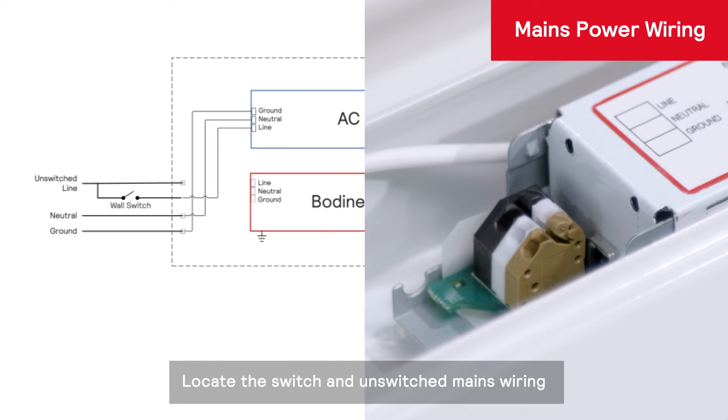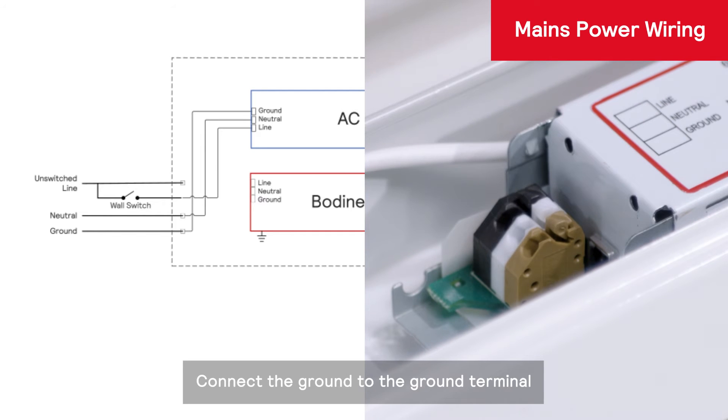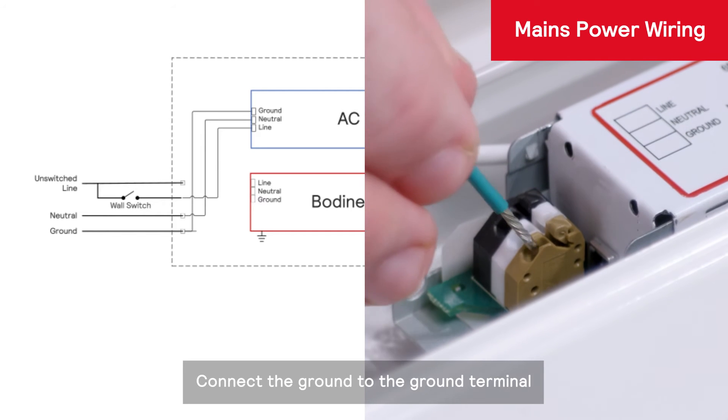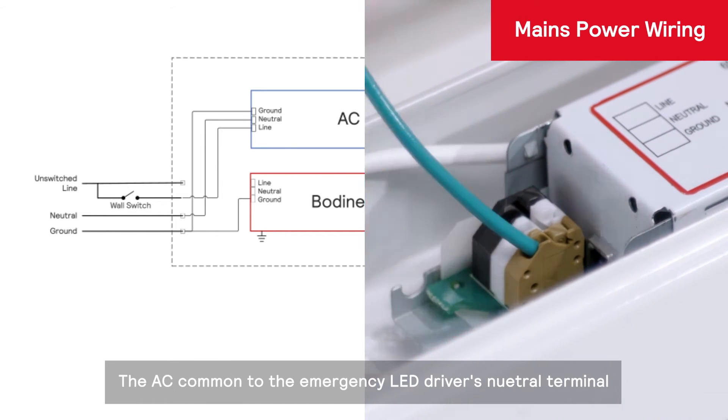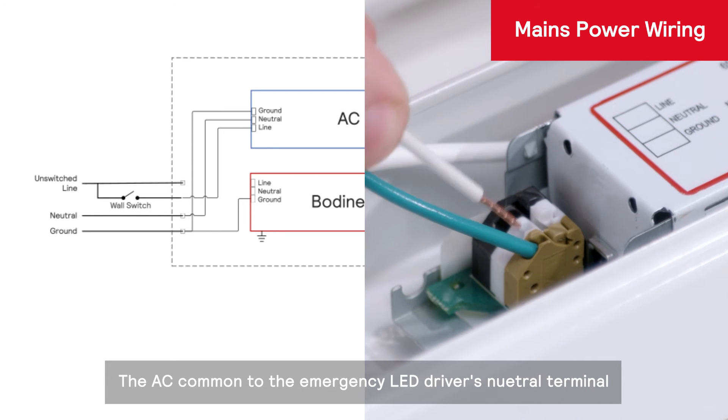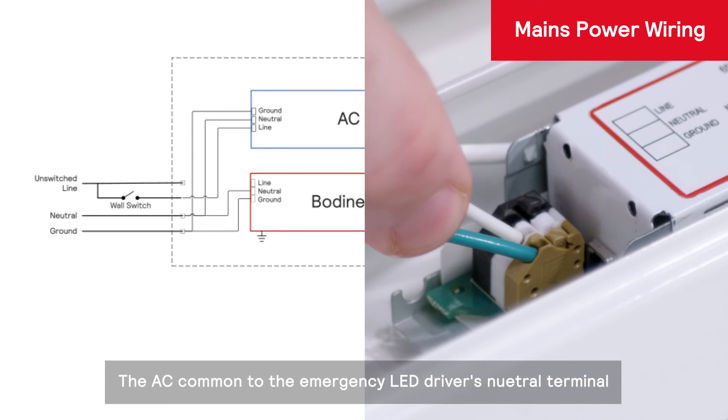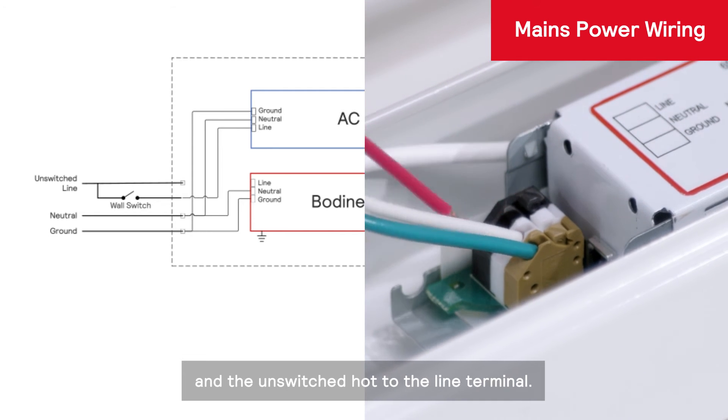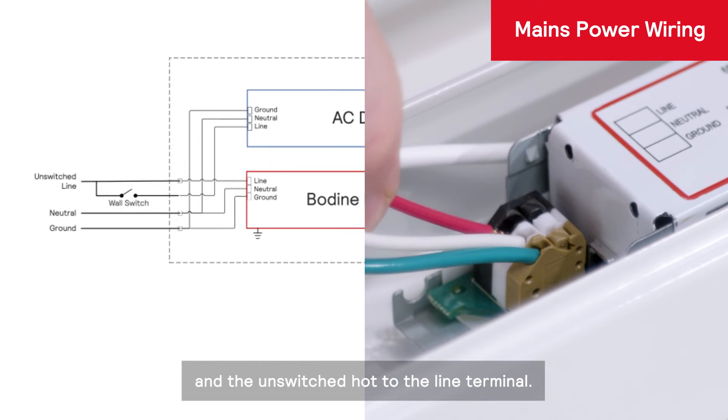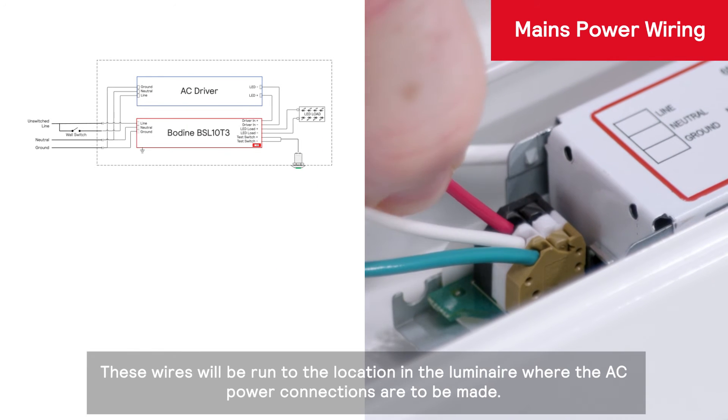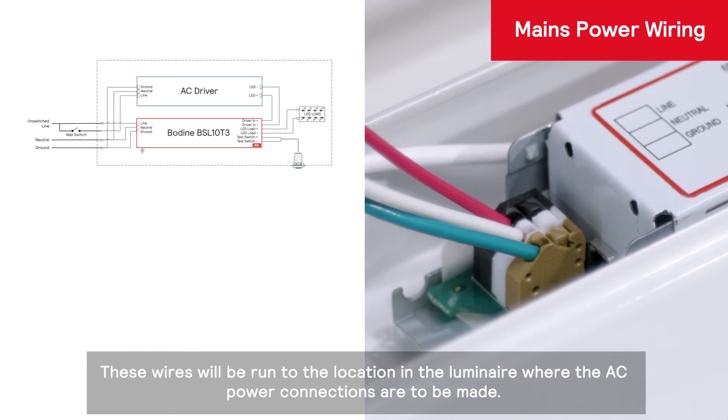Locate the switch and unswitched mains wiring. Connect the ground to the ground terminal. The AC common to the emergency LED driver's neutral terminal and the unswitched hot to the line terminal. These wires will be run to the location in the luminaire where the AC power connections are to be made.